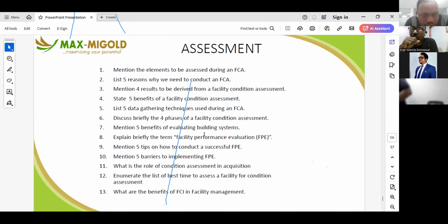So when your condition assessment tells you that you have a pump that is already vibrating, a roller that is almost giving way, and a bearing that is already generating heat, first of all you need to put all these things in good shape. Having done that, what condition monitoring devices do you need to put in place to ensure that these things are always available as and when needed?